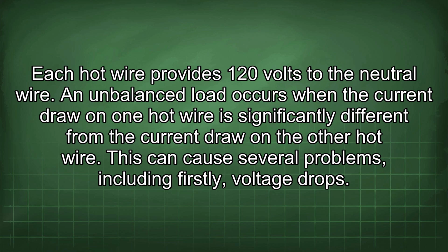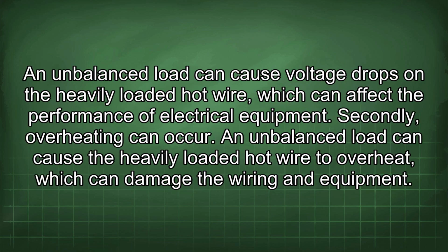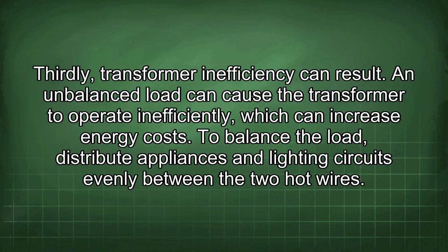An unbalanced load occurs when the current draw on one hot wire is significantly different from the current draw on the other hot wire. This can cause several problems, including, firstly, voltage drops. An unbalanced load can cause voltage drops on the heavily loaded hot wire, which can affect the performance of electrical equipment. Secondly, overheating can occur. An unbalanced load can cause the heavily loaded hot wire to overheat, which can damage the wiring and equipment. Thirdly, transformer inefficiency can result. An unbalanced load can cause the transformer to operate inefficiently, which can increase energy costs.